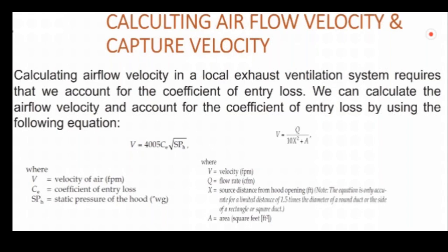If we look at this formula, V is equal to 4005 times CE times the square root of SP. CE is the coefficient of entry losses at the hood, and SP is the static pressure at the hood.